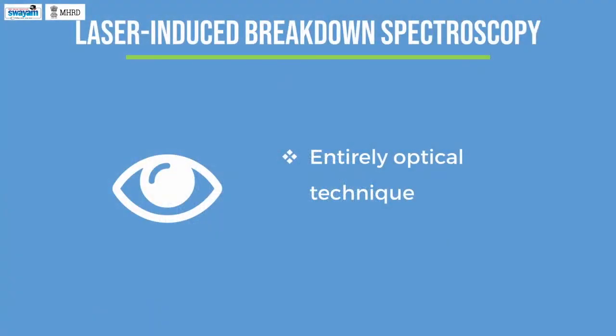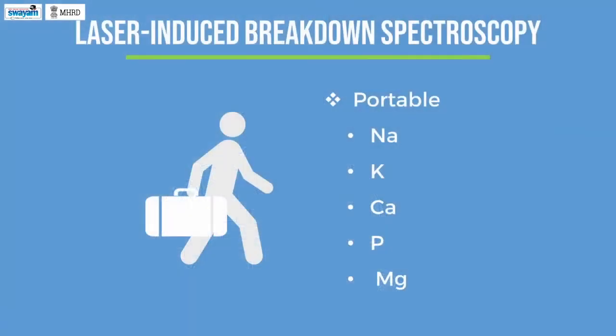Since LIBS is an entirely optical technique, we can analyze samples even without touching them, just by focusing the laser onto the sample. Additionally, a LIBS system can be coupled to an optical microscope for mapping elements present in a given sample. Unlike conventional AES techniques, this LIBS instrument is portable and can be used for screening samples for a variety of elements, particularly lighter elements such as sodium, potassium, calcium, phosphorus, and magnesium.